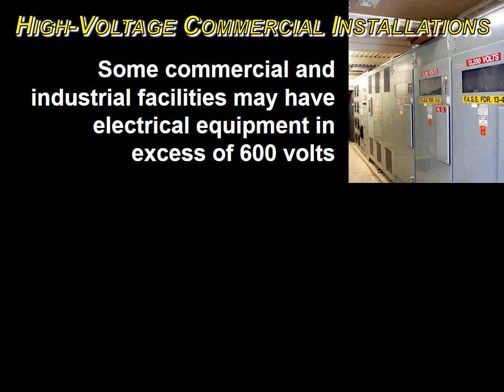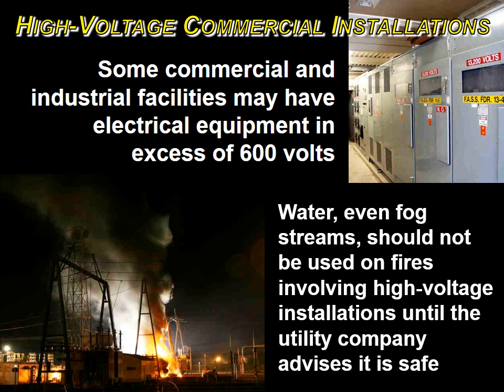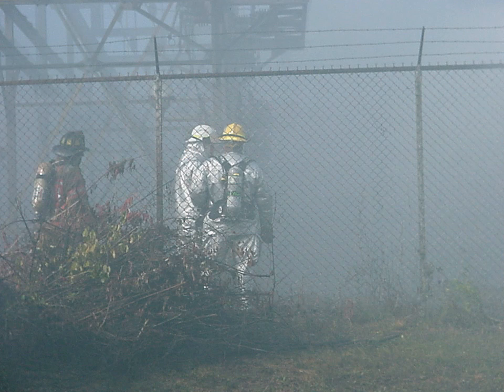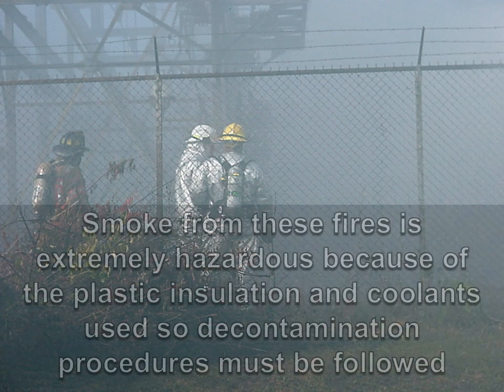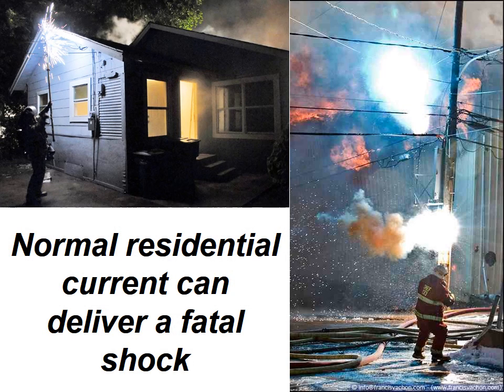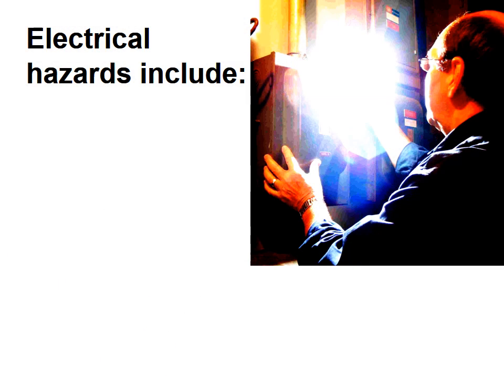In high voltage commercial installations, some commercial and industrial facilities may have electrical equipment in excess of 600 volts. Water, even fog streams, should not be used on fires involving high voltage installations until the utility company advises it is safe. Smoke from these fires is extremely hazardous because of the plastic insulation and coolant used, so decontamination procedures must be followed. Normal residential current can deliver a fatal shock. Electric hazards include cardiac arrest, respiratory arrest, paralysis, joint damage, arc burns to eyes, ventricular fibrillation, surface or internal burns, and involuntary muscle contractions.